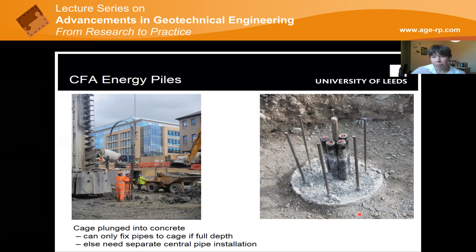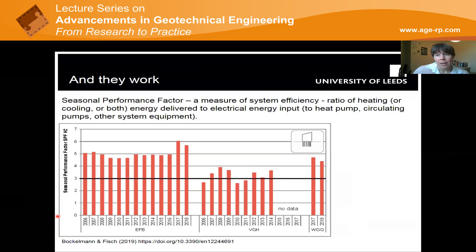It's important to say that these energy pile solutions do work in terms of delivering energy. This is some data on seasonal performance factor from some German energy pile schemes. Seasonal performance factor is basically a measure of system efficiency - a ratio of how much heating energy is delivered compared to how much electricity you have to put in to run the heat pump and maybe the circulation pumps. You really should be trying to achieve about 3. In these German case studies there are 1, 2, 3 buildings monitored over a number of different years, and they're pretty much all hitting that seasonal performance factor of 3. So you really are getting a successful energy system.